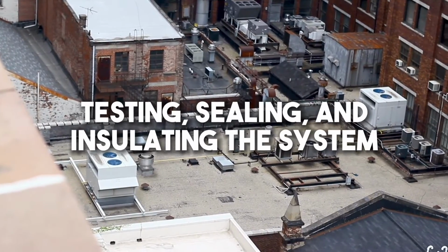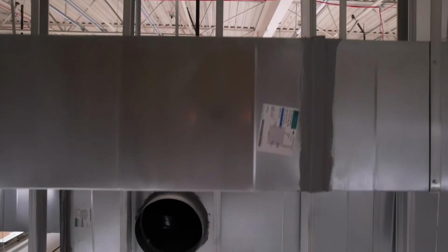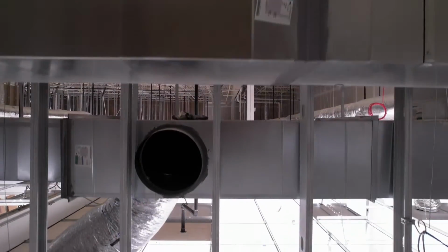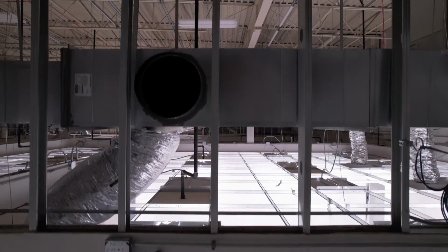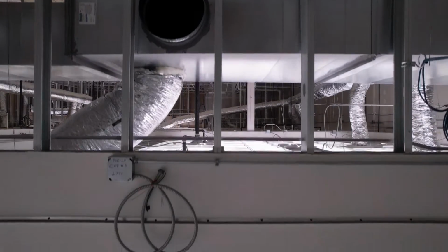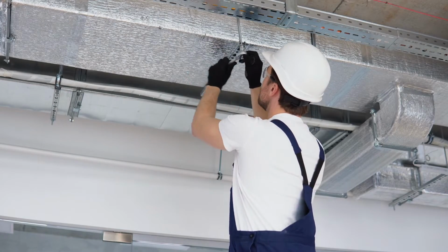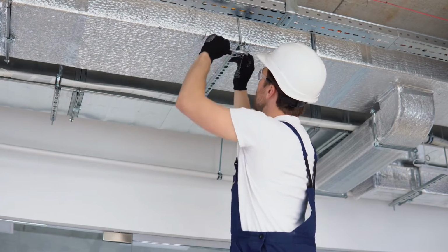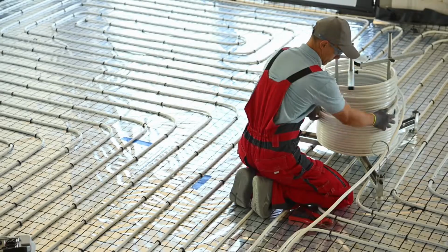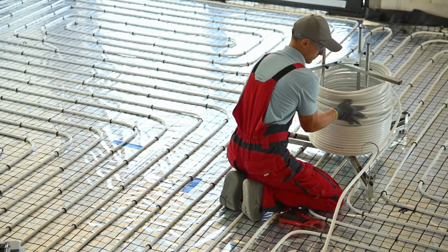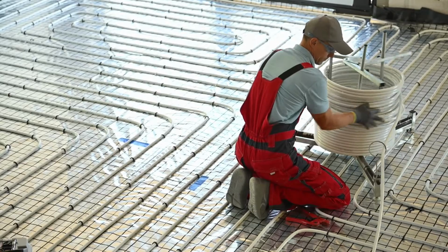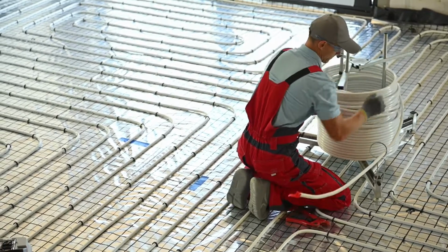Testing, sealing, and insulating the system. After connecting the indoor and outdoor units, testing the system's electrical wiring and refrigerant lines is necessary. Once everything is connected, it's essential to test the system with a multimeter to ensure it's in proper working order. Sealing and insulating your ducts and piping with non-flammable insulation materials will help your mini split system run more efficiently and reduce noise levels.